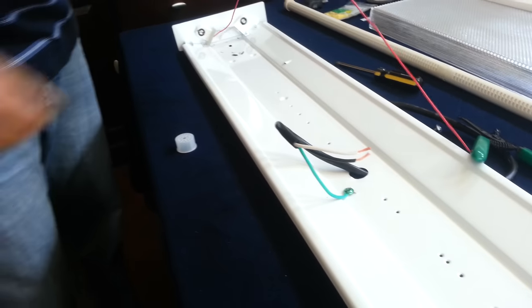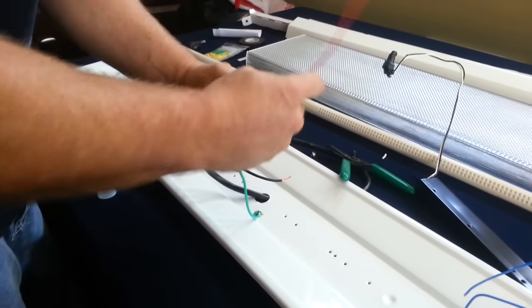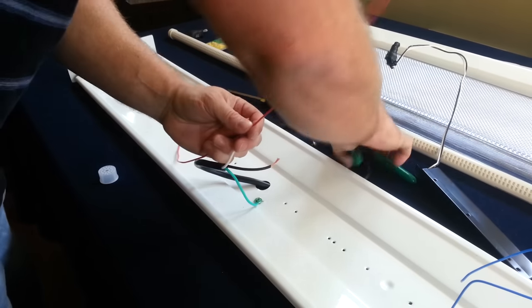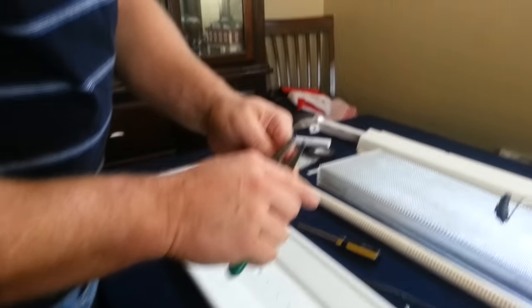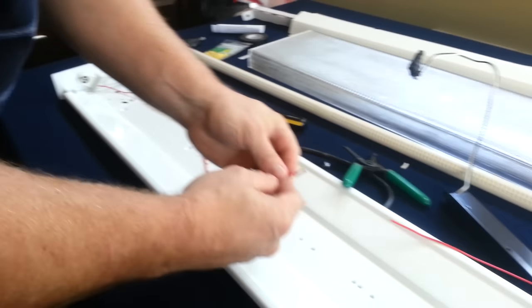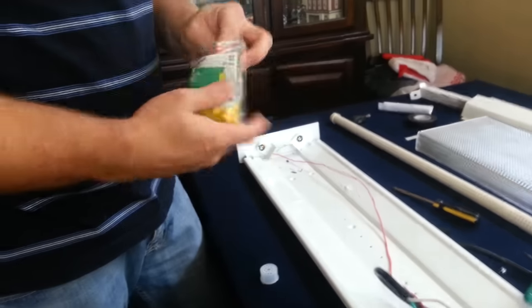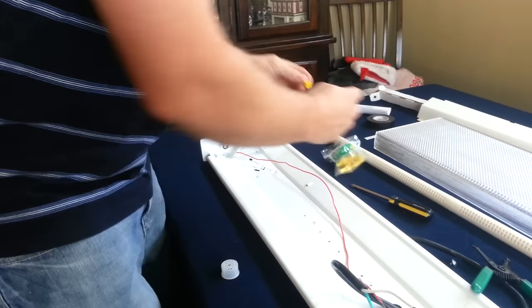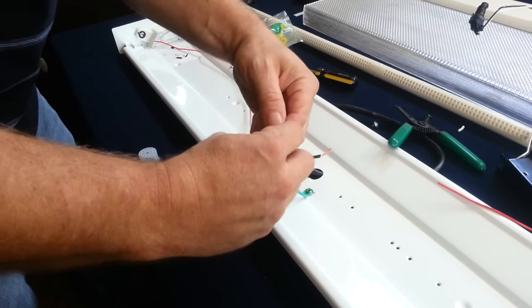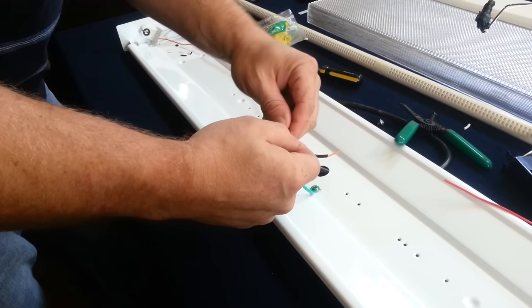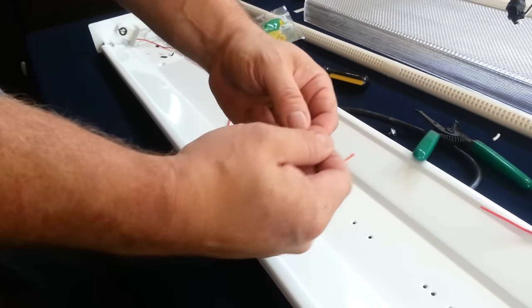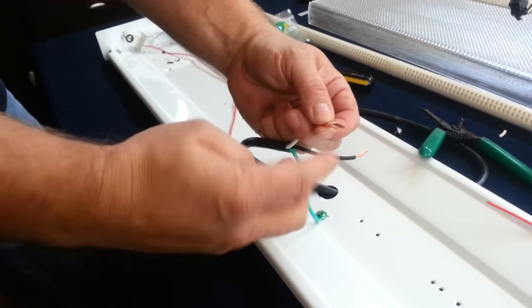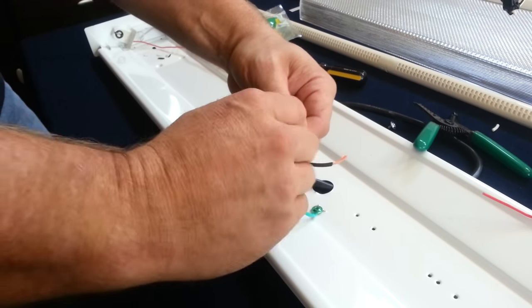Then again, one side of the wires goes to hot, the other side goes to neutral, or vice versa. So what we'll do here is we'll cut ourselves plenty of excess wire here. We'll strip that down to about a half an inch, and we're going to wire them together using some wire nuts. Any time you wire a stranded wire to a solid, it's a good idea to leave your stranded wire about an eighth of an inch to a quarter of an inch above your solid. And just wire nut them together like so.